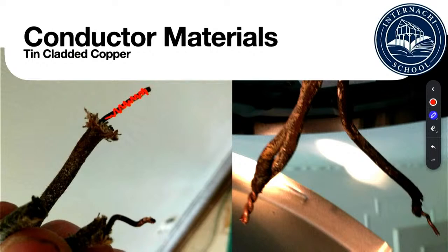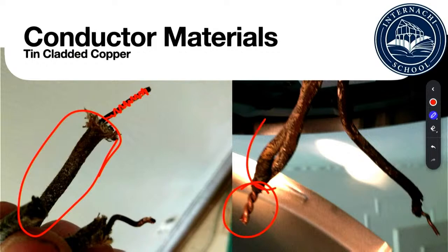The dead giveaway of this is the cloth jacketed insulation. I'm not aware that these wires were ever manufactured with plastic insulation. We really don't use tin for cladding anymore; copper seems to be the preferred metal now. Even though this looks like copper, I believe the tin was worn or rubbed off of it. If you see a silverish conductor with cloth insulation, that is tin clad copper.